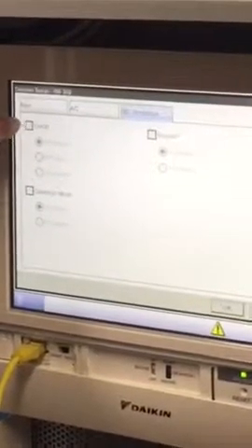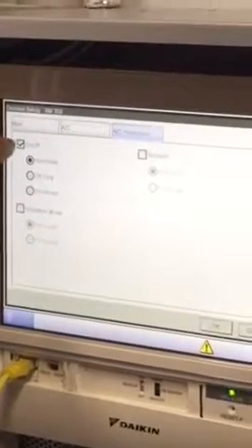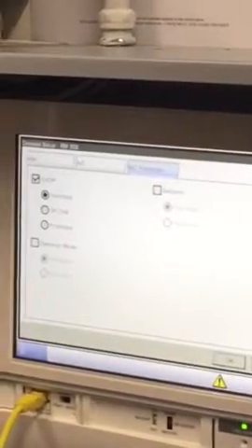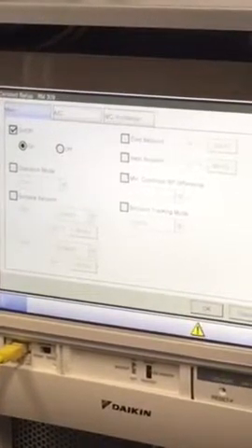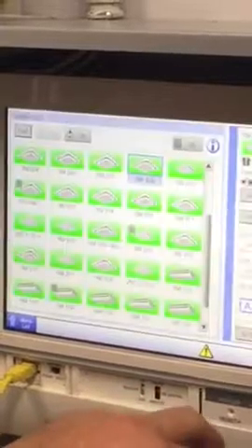Or you can completely lock it out from this screen by telling it, I'm going to prohibit somebody from turning this unit on and off, or changing the operation mode, or adjusting the set point. So you really can't do anything to screw anything up right here. This is just kind of a menu for you to lock out some options on the nav controller, is what you're doing.